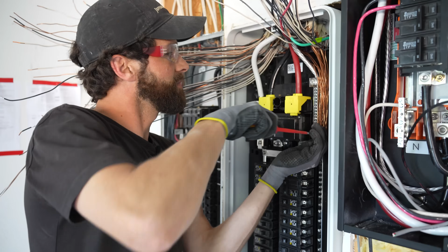This process is just painful, or painstaking is better. Lacing into the panel, I'm doing grounds first, then neutrals, then I'll terminate all the hots. As I'm terminating the hots, I need to make sure when cutting and stripping the wire, I preserve the labels so I've got total clarity on what that is, because having to jump in the house and trace things out is extremely time consuming.